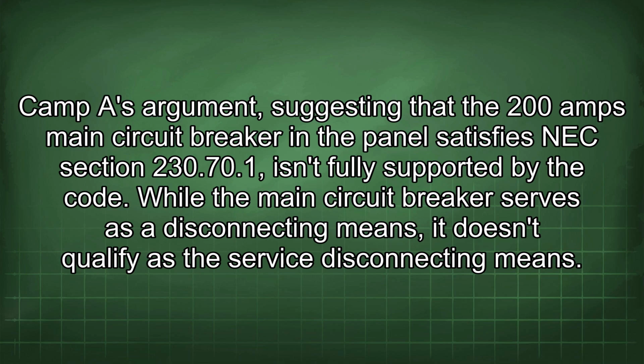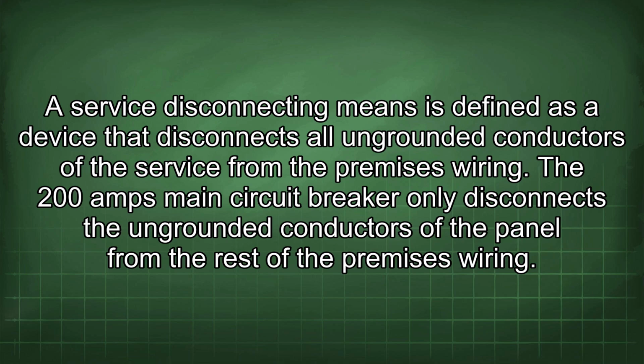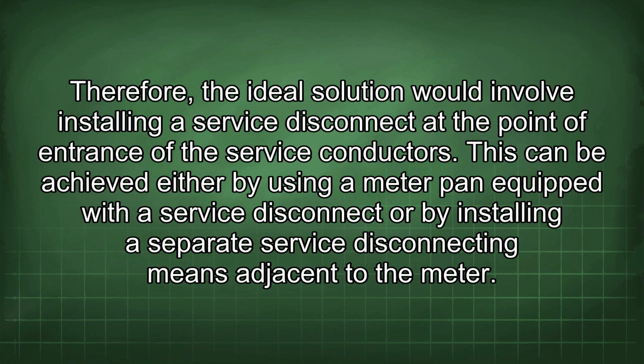While the main circuit breaker serves as a disconnecting means, it doesn't qualify as the service disconnecting means. A service disconnecting means is defined as a device that disconnects all ungrounded conductors of the service from the premises wiring. The 200 amps main circuit breaker only disconnects the ungrounded conductors of the panel from the rest of the premises wiring. Therefore, the ideal solution would involve installing a service disconnect at the point of entrance of the service conductors. This can be achieved either by using a meter pan equipped with a service disconnect or by installing a separate service disconnecting means adjacent to the meter.